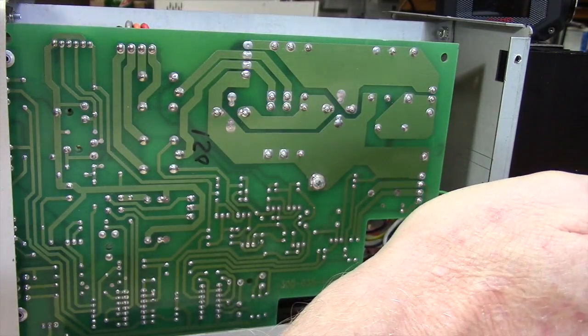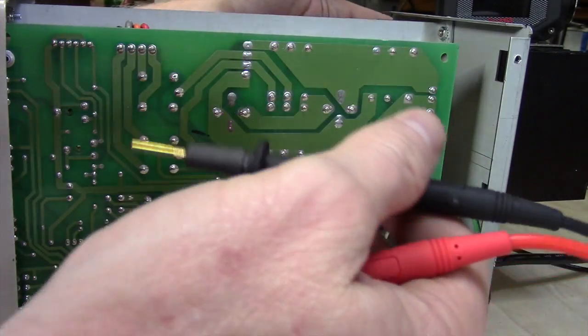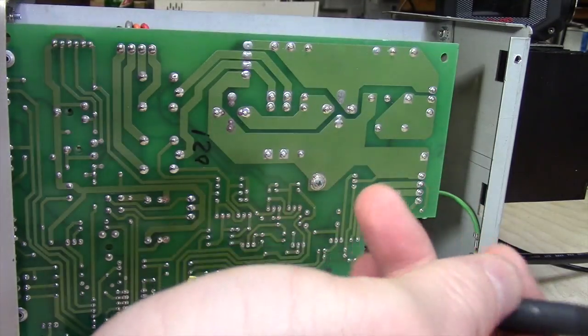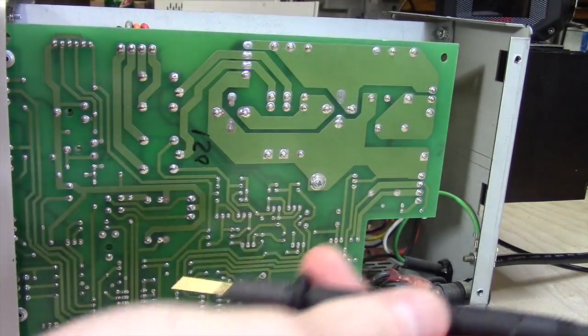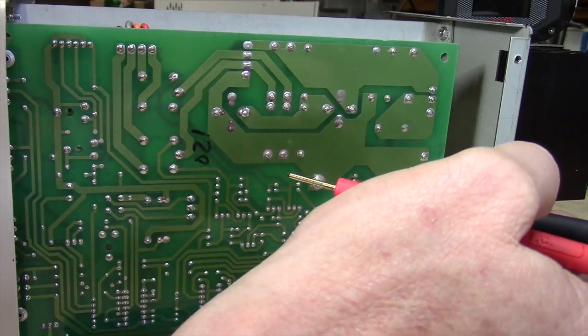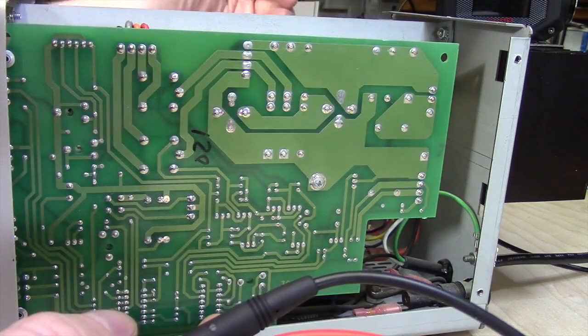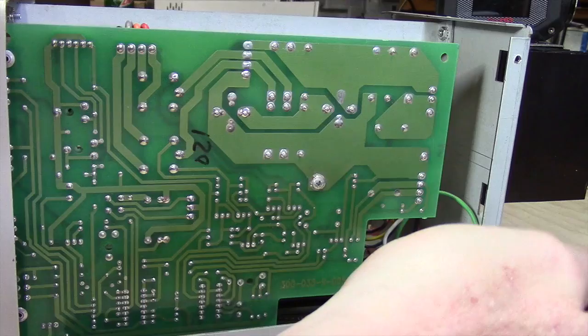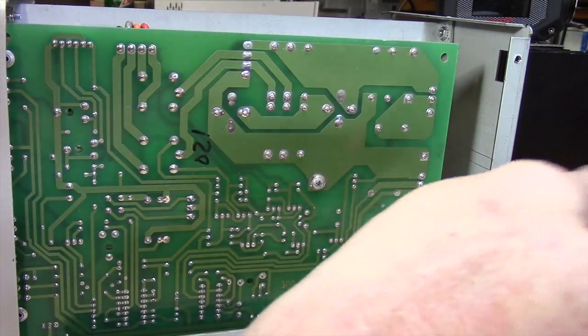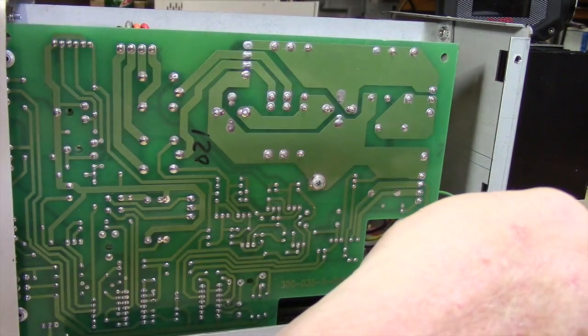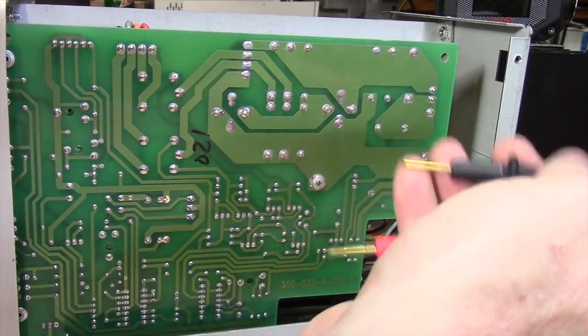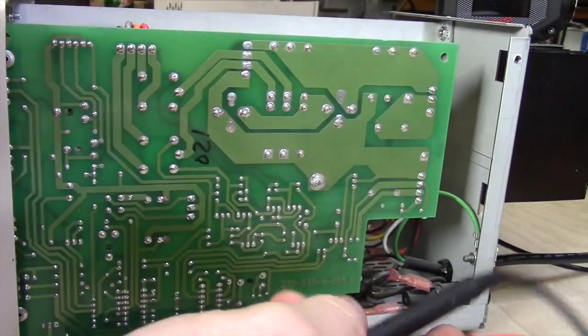So this is more than likely not going to be an electrical problem. This is going to be, or is an electrical problem. More than likely, this is going to be an issue of the AC input into the transformer. Now that could be the cord. We've already checked the fuse, but there could be some connectivity issues. The quickest way to check that is to actually do a continuity test to see where the failure is occurring. And we're going to do that now.